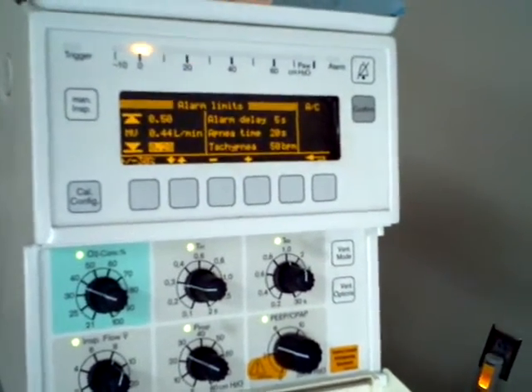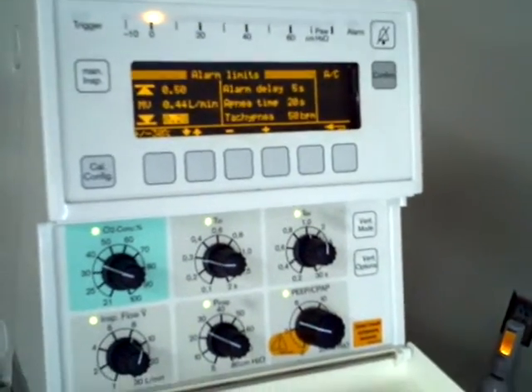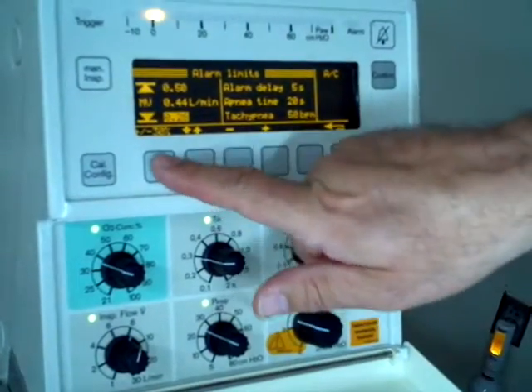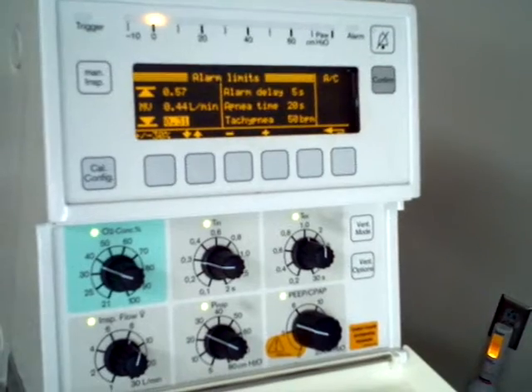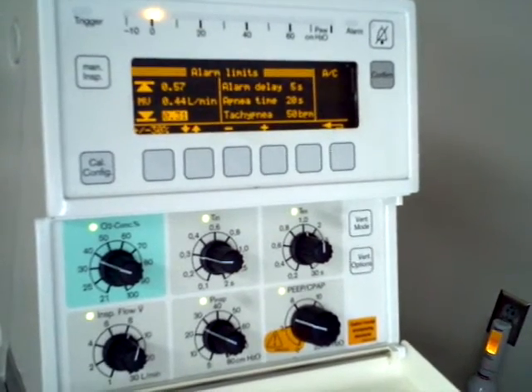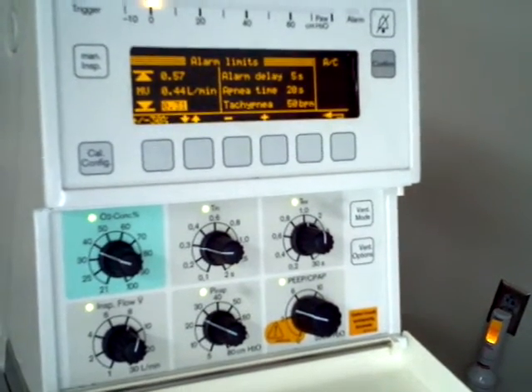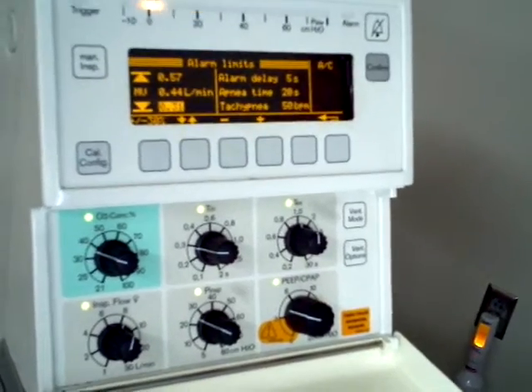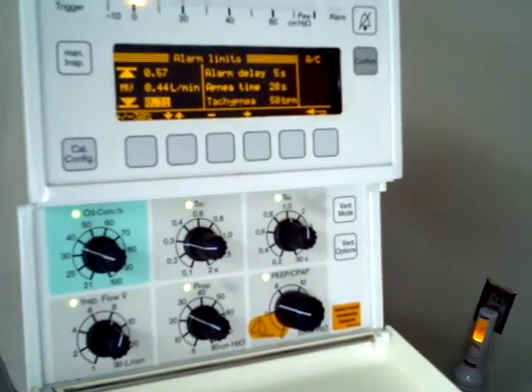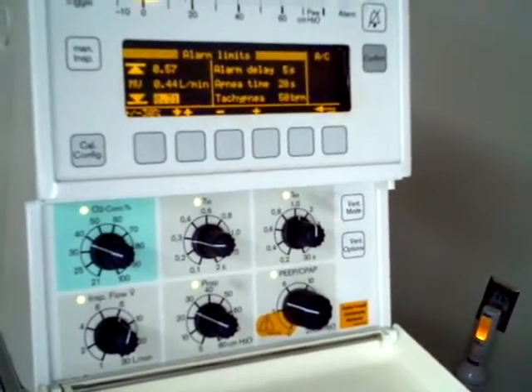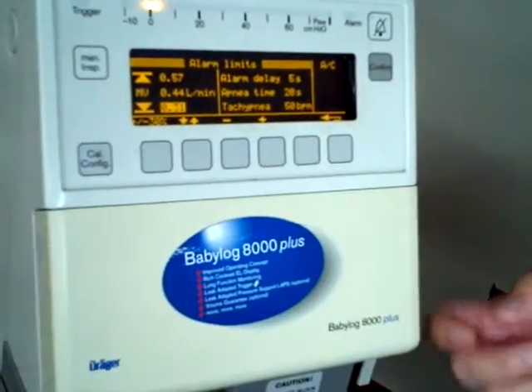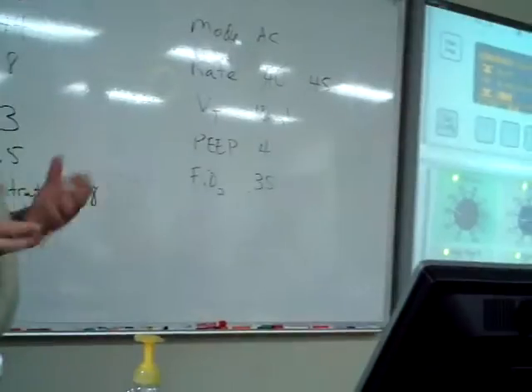Went up, right? We turned up the rate. More breaths, more minute volume. I'm just going to set plus or minus 30% on my minute volume alarm. We should be done with that section because our tidal volume stayed the same. Change ventilator to new rate. Another new rate. A lot of our ventilator changes are rate changes, so we've got a few on this checkup.